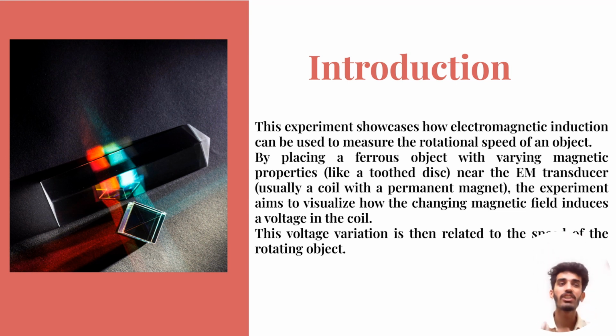This experiment showcases how electromagnetic induction can be used to measure the rotational speed of a shaft by placing a ferrous object with varying magnetic properties, like a toothed disc with slots, near the electromagnetic transducers, that is, near the electromagnetic pickup sensors. Usually these are a coil with a permanent magnet inside it. Near the EM transducer, we aim to visualize how the changing magnetic field induces voltages in the coil via Lenz's law. This voltage variation is then related to the speed of the rotating shaft.